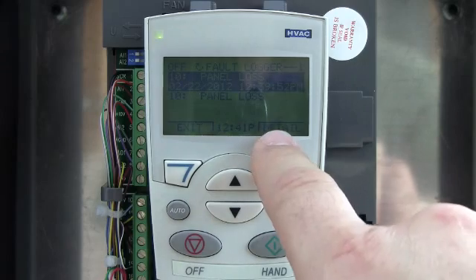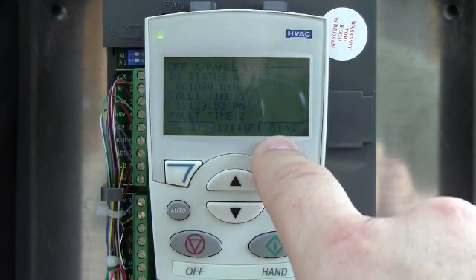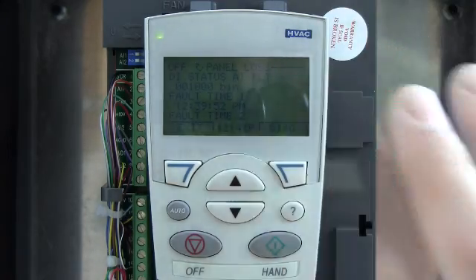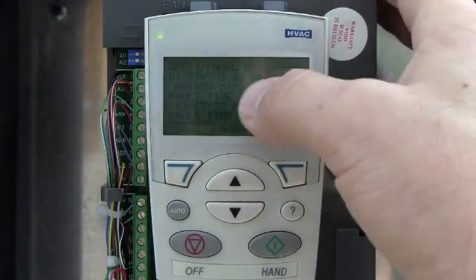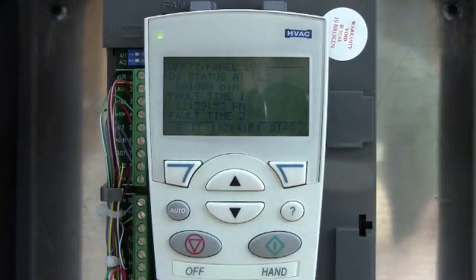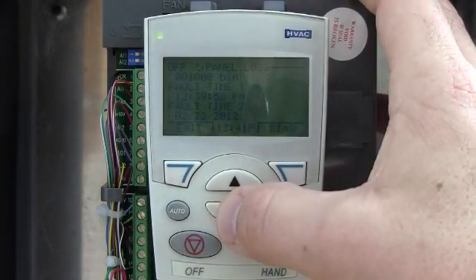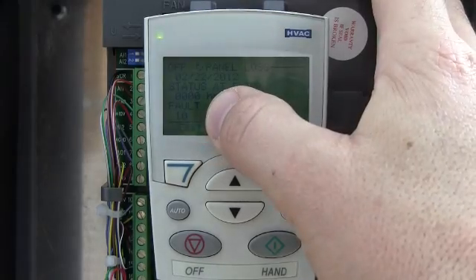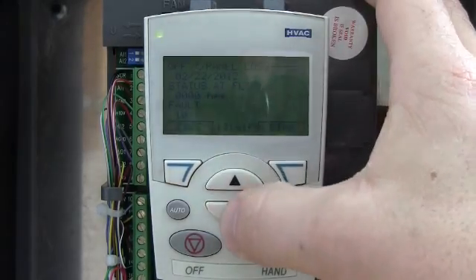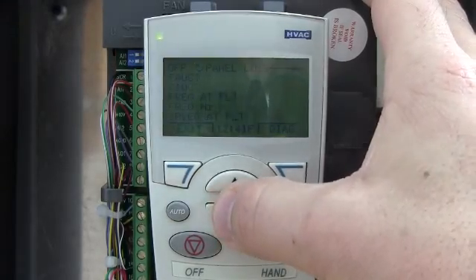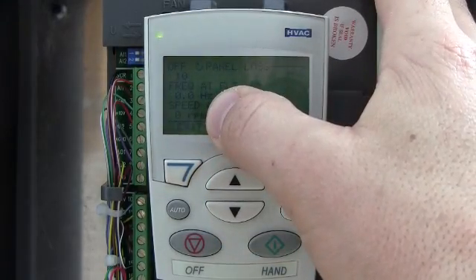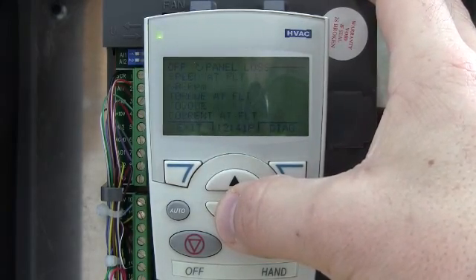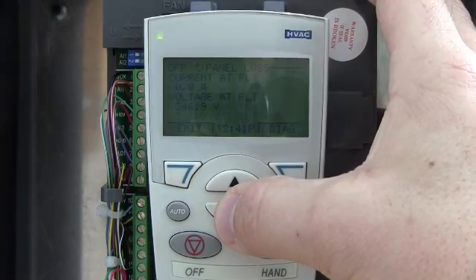What's nice about this is if you look at this detail and push that, you can actually see what state the drive was in when it tripped. It will tell you things like what all your digital inputs were — basically your terminal strip ins and outs. If you push the down arrow, it will tell you the time and date, your status at fault in hex code, the fault number, frequency, what speed the drive was running at when it tripped, the percent rated speed, torque, current, and voltage.